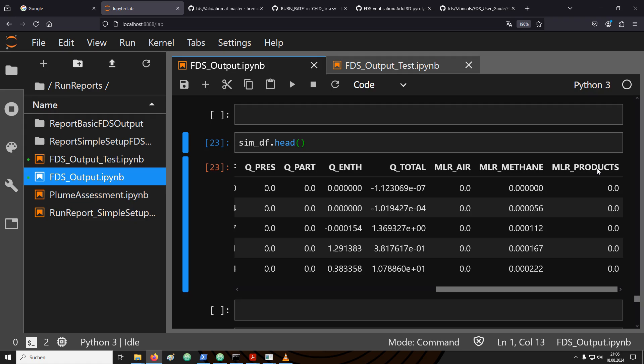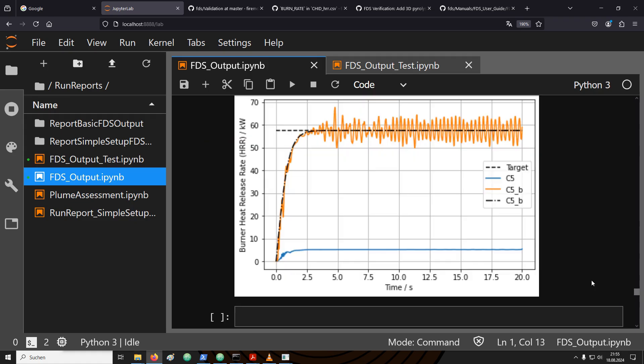Just be aware that the values from the HRR column and the mass loss rate multiplied with heat of combustion do not necessarily have to match. For example, you could have a situation where some of the combustible gas leaves the domain before being burned. This would then not show up in the HRR column. There, only the heat released inside the computational domain will be tracked.